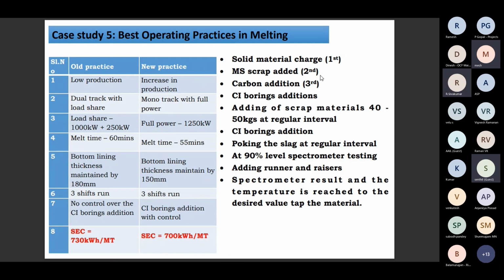Best operating practices in melting, same thing. This one is dual track furnaces with load share, mono track with full power, and the load sharing is happening. Earlier it was 1000 kilowatt plus 250 kilowatt. Now it is given as full power, 1250 kilowatt. The main thing here is that the solid material is charged first, then the MS scrap is added, and the carbon addition is third. Then CI borings are added, adding the scrap materials 40 to 50 kgs at regular intervals, and the CI borings addition. And the main thing is poking the slag at regular intervals, so the slag is removed periodically and poking is done as a regular practice.